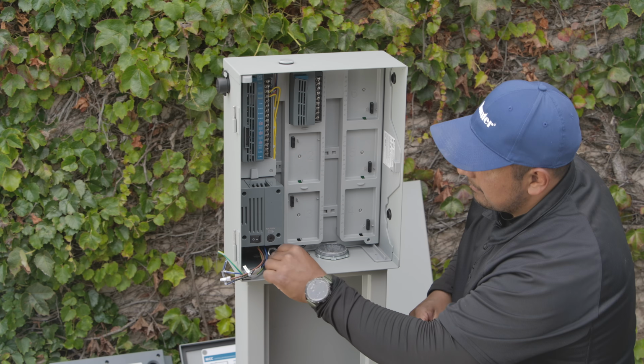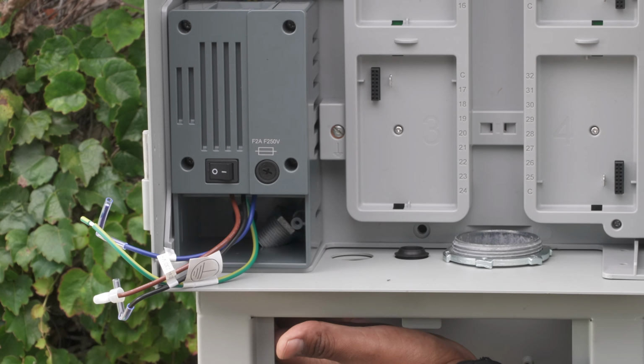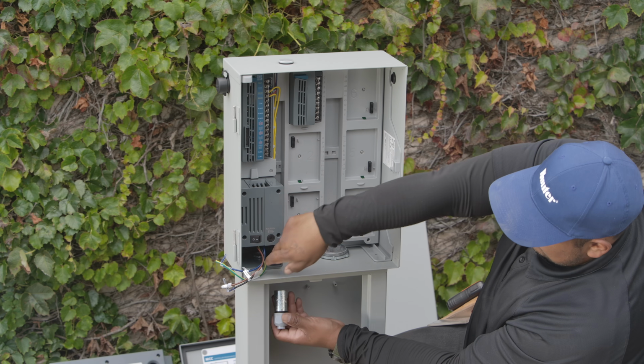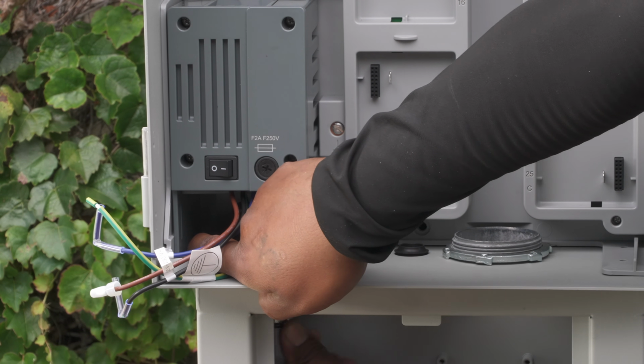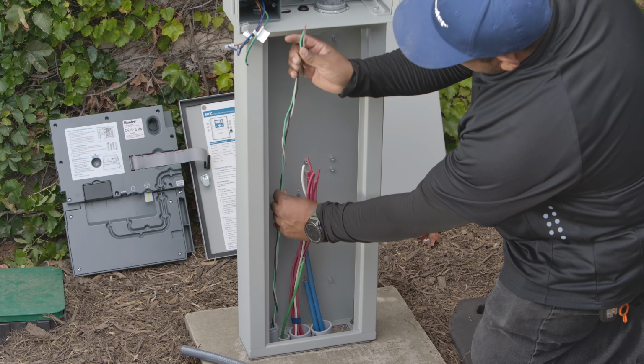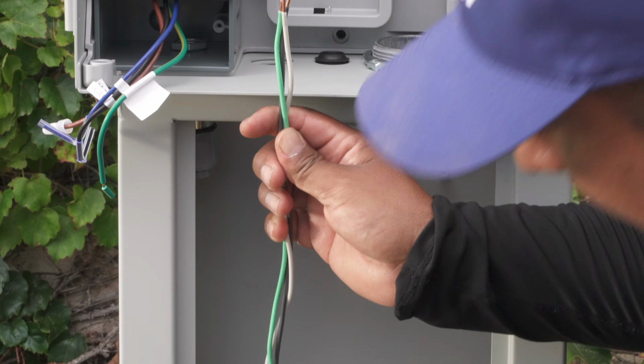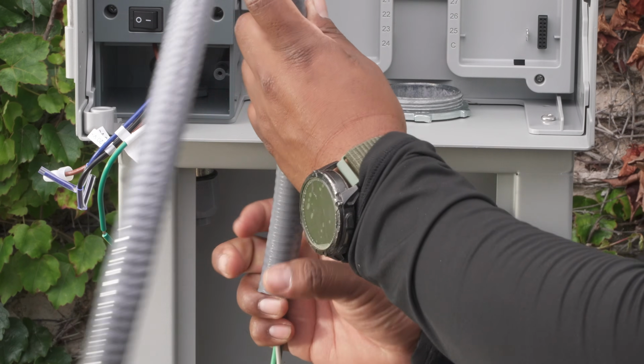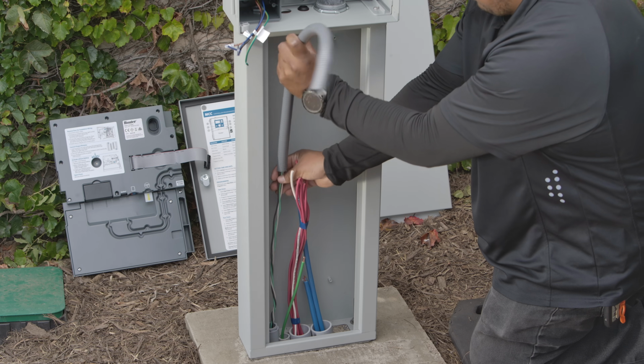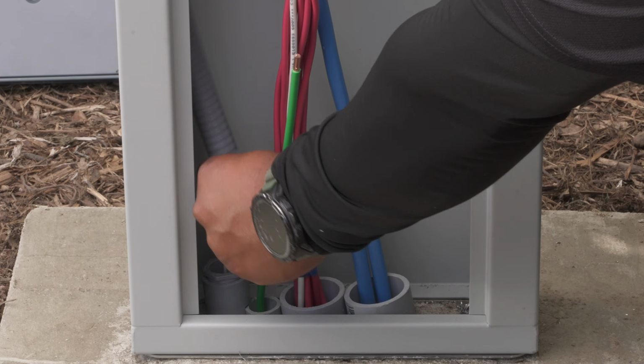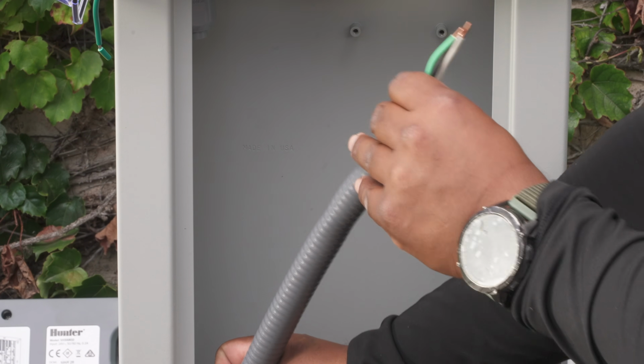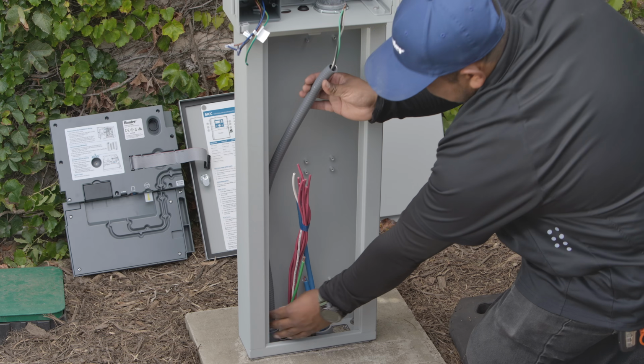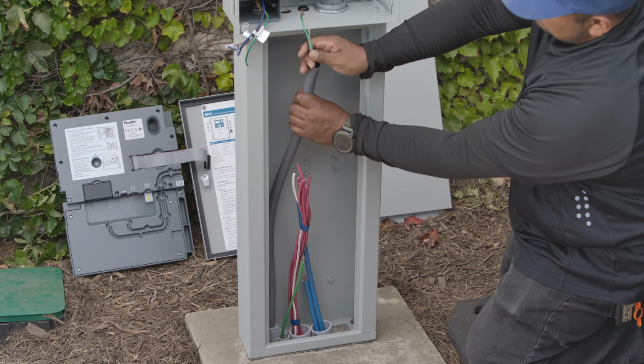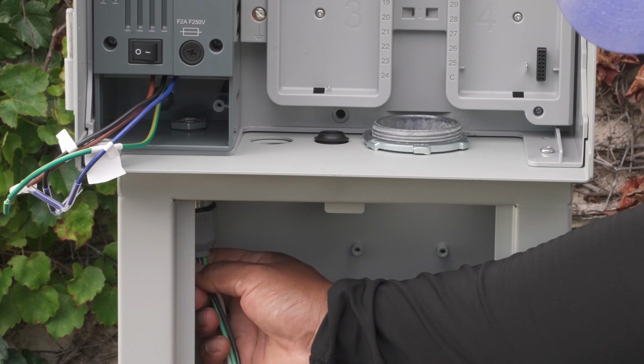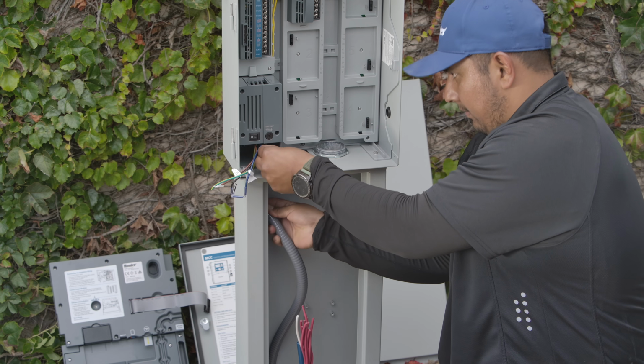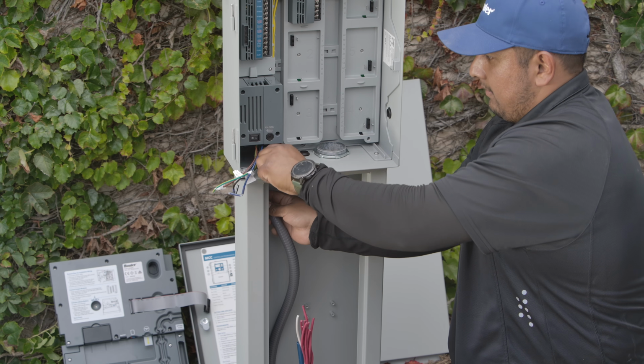In metal enclosures, you might need a slightly extended nipple to get enough thread engagement to secure the conduit. Measure and cut the electrical conduit to reach from ground level to the bottom of the controller. Route the electrical wiring from the bottom up into the wiring compartment, and leave enough wire above the conduit to complete the electrical connections. Secure the conduit in the wiring compartment with the included conduit nut.